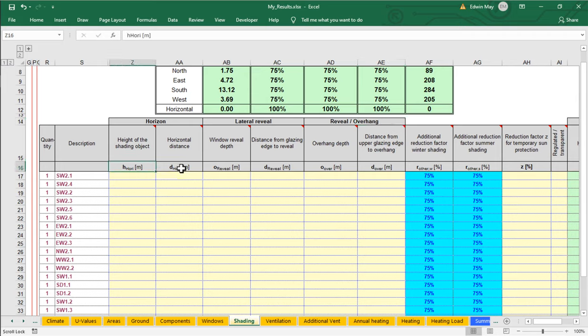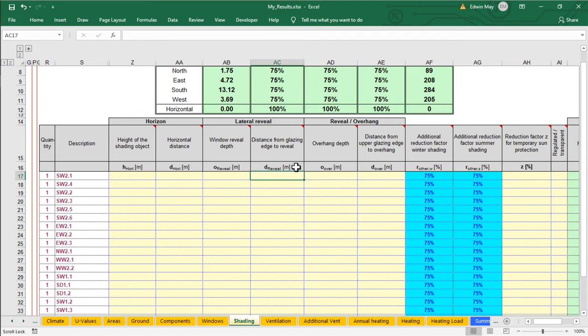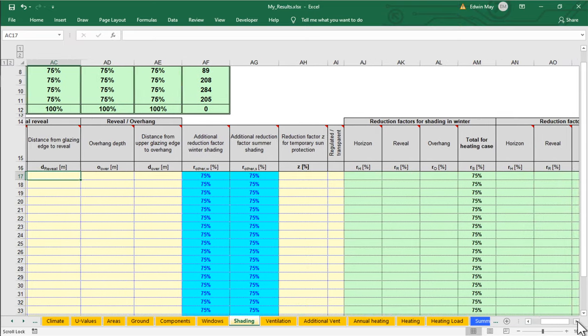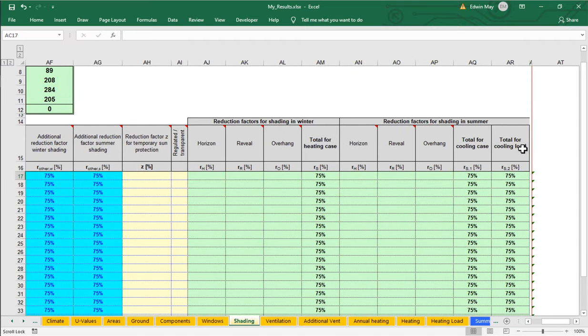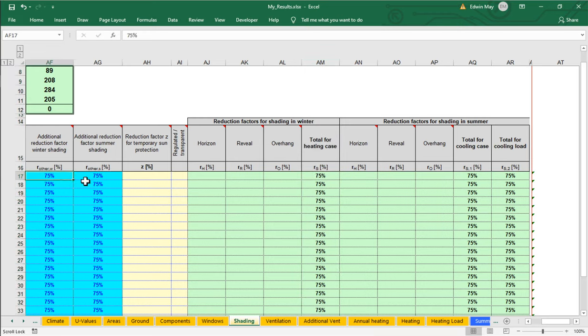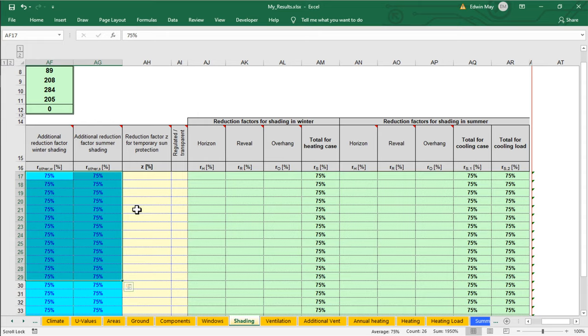And notice the inputs are all in meters. If you're working in IP, they would be in feet. But in this case, we are in meters. In any event, it's a dimension. It's a distance. So what we input is a bunch of distance or dimensional information. That is all in the PHPP, in this worksheet. It's all combined together in order to calculate a total reduction factor. So way over on the right-hand side here, you can see we have a total reduction factor for the cooling case and a total reduction factor for the heating case. Right now, they're all set to 75% because you can see here we are setting everything to 75% as a default, just a constant.